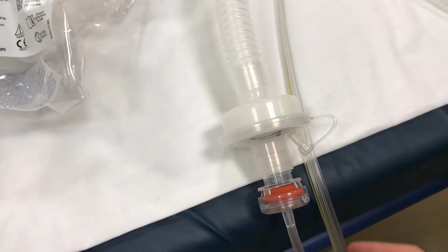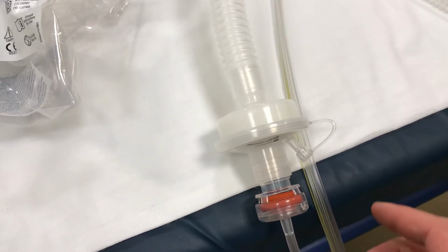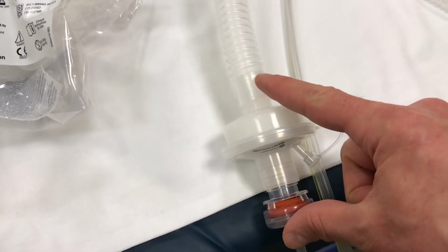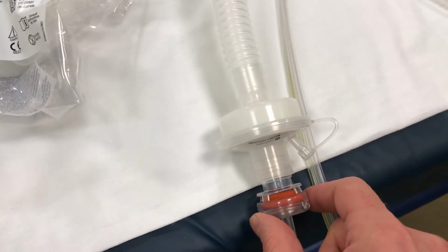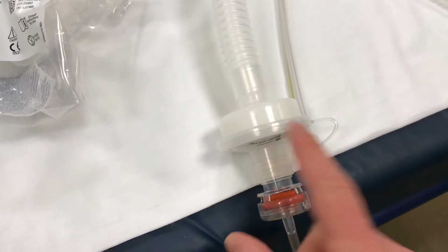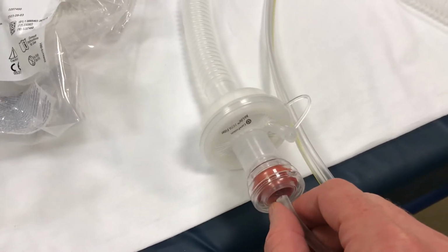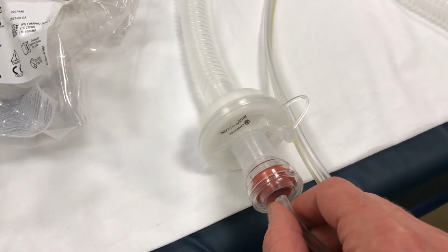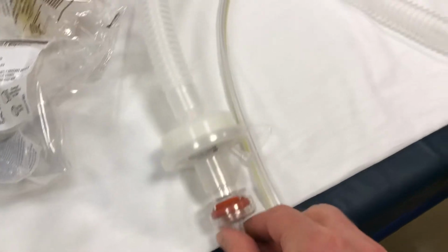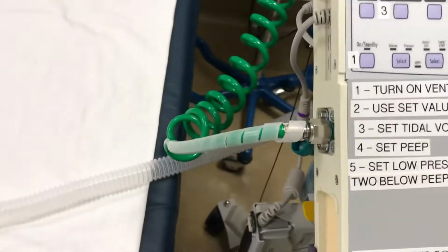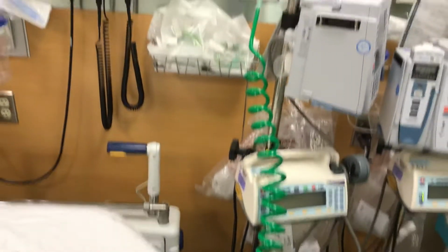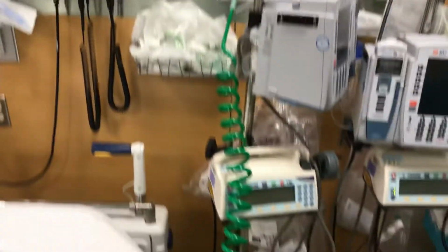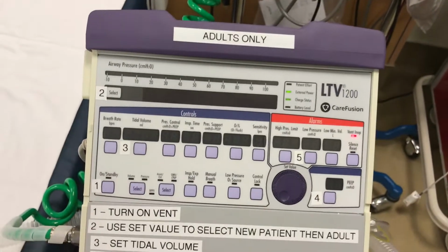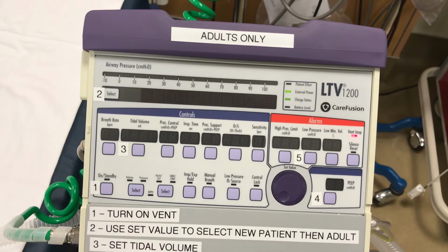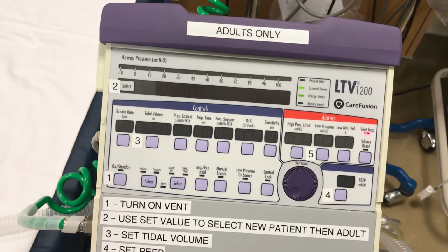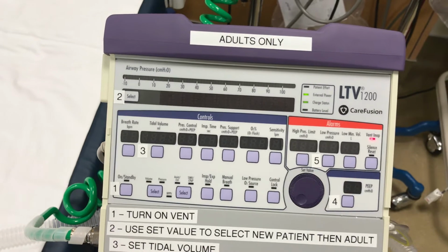When you unpack the patient's circuit from the bag, you'll have to disconnect the corrugated tubing from the expiratory valve to place the viral filter. Fortunately, filters only fit one way, and that's the correct way. Make sure that your oxygen source is connected. However, the LTV does have an internal compressor and can generate rather high flows.